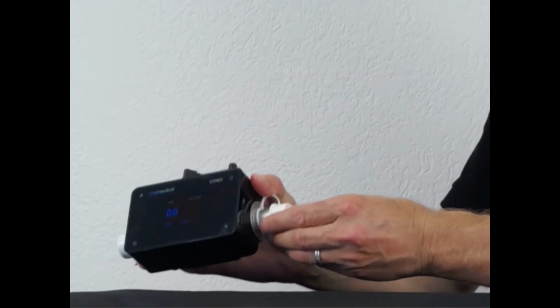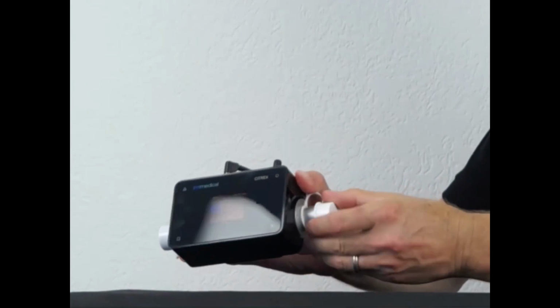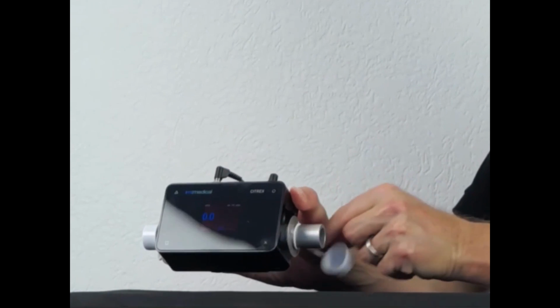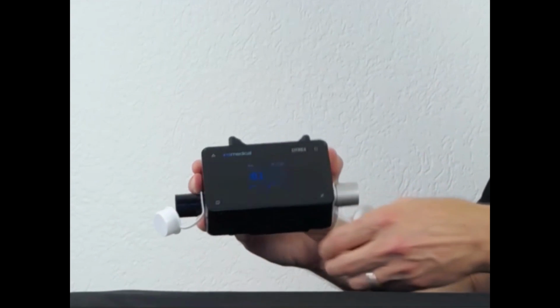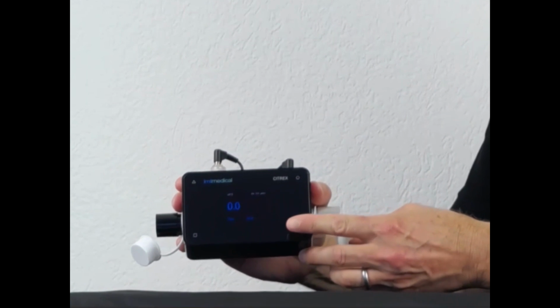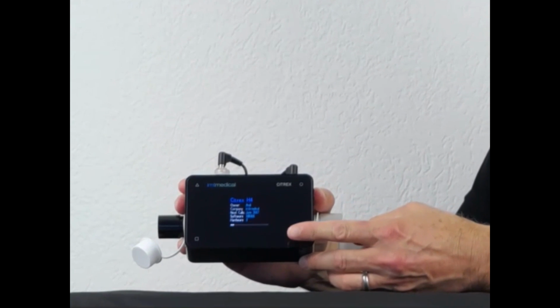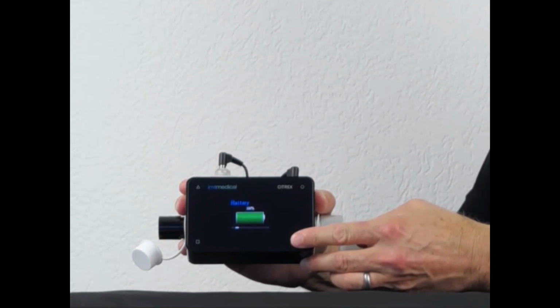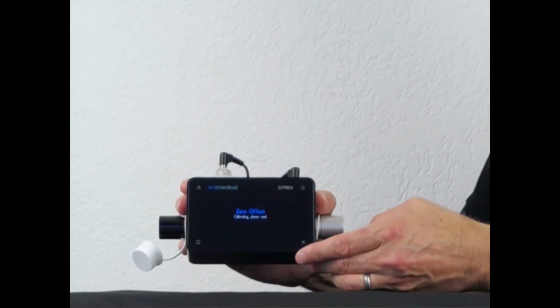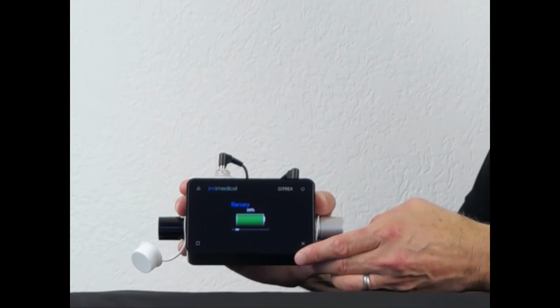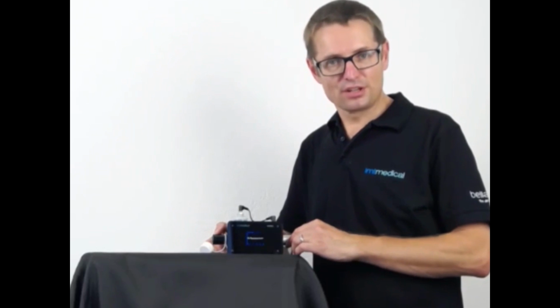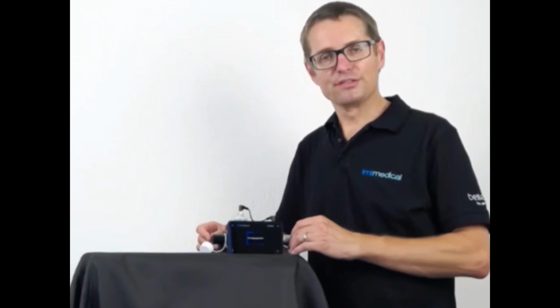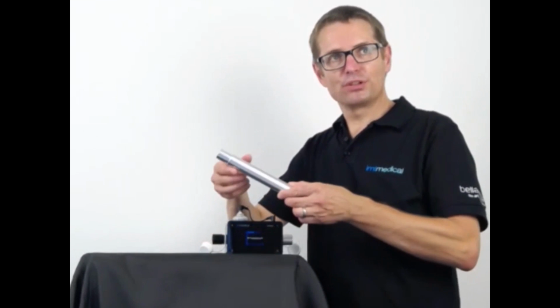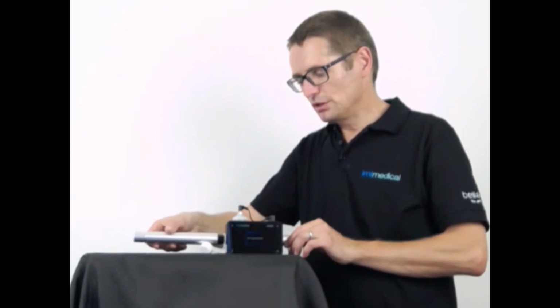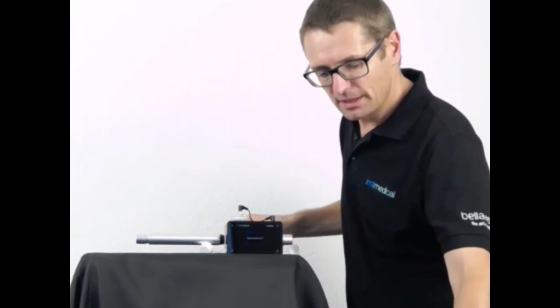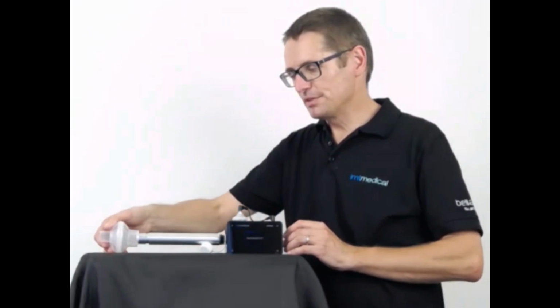This is the CITREX, and it is protected with these white caps, which now have to be removed before we do any zero operation. Then we use this button here, so we access the service menu, and when we click it long, it will automatically start the zero procedure. The zero procedure just takes a few seconds. After performing the zero, we are ready to do the setup of the device. Very important is the laminarization tube, which laminarizes everything on the inlet, and on top of that comes the inlet filter.